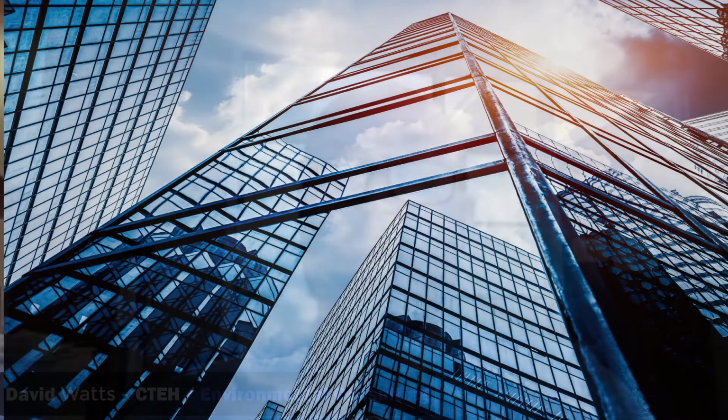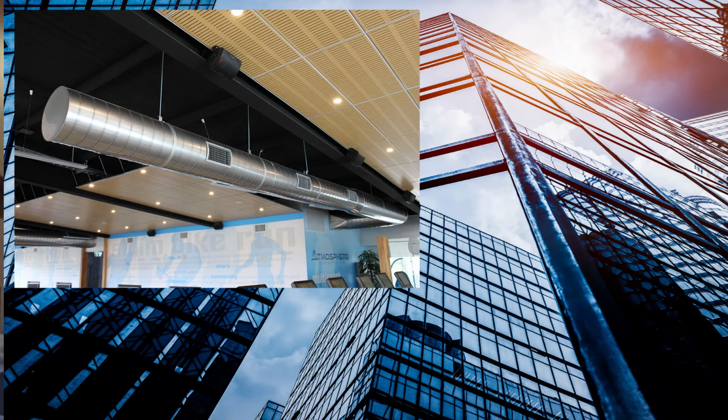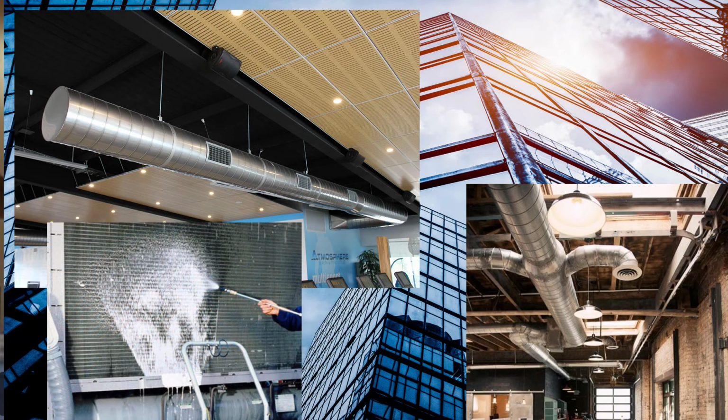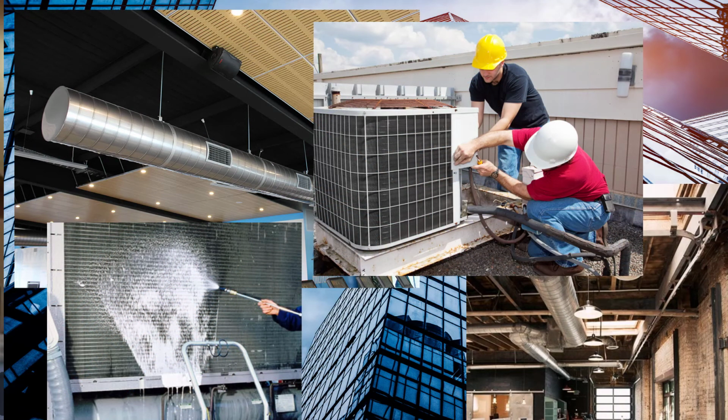Yeah, sure, Matt. There actually may be certain contact points which warrant cleaning, such as thermostats or return grills or supply air diffusers. However, complete cleaning of the HVAC may not be necessary. And given that many of these HVAC systems will have sat idle or offline or even not received routine maintenance or servicing for weeks or months, it's really important that building owners have these systems assessed for cleanliness. There's likely going to be accumulation of some mold or biological growth in these systems, such as evaporator coils and condensate pans and some of the mixing chambers.